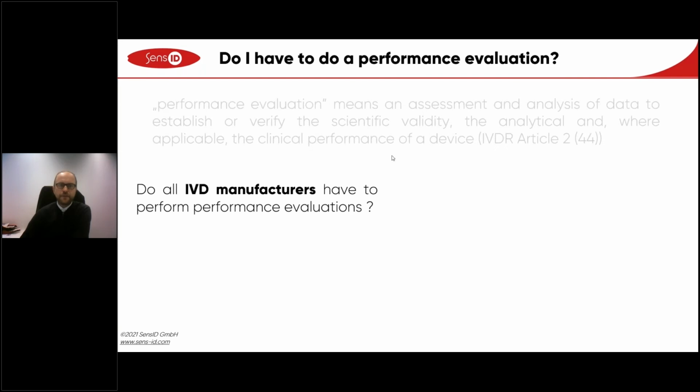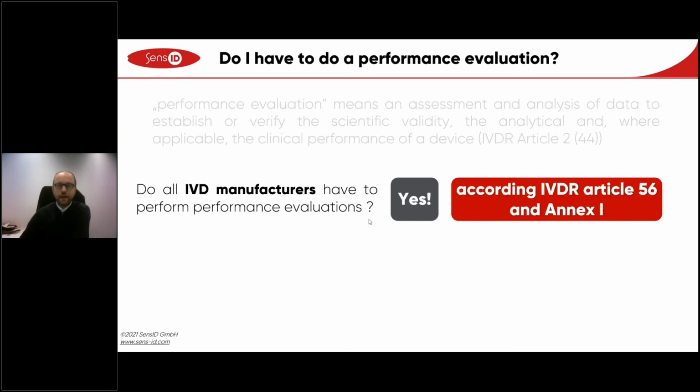And we can ask two different questions here, actually: IVD manufacturers or LDT manufacturers, do you have to perform a performance evaluation? And the simple answer for IVD manufacturers, yes, of course. This is according to IVDR Article 56 and Annex 1.